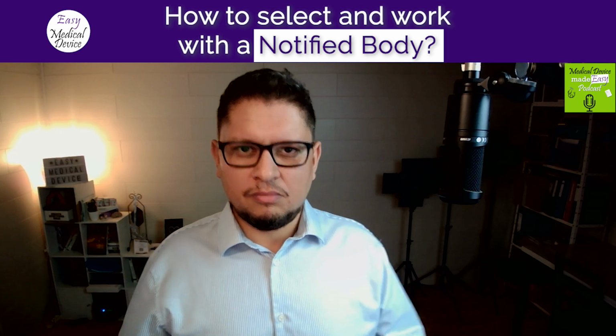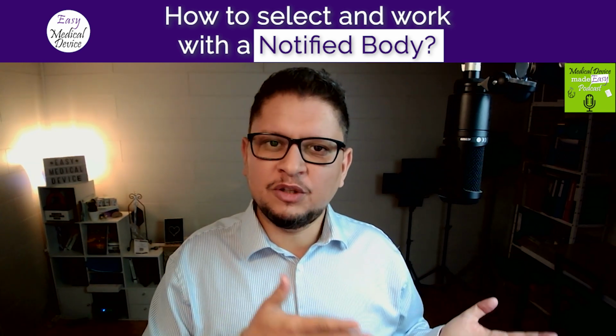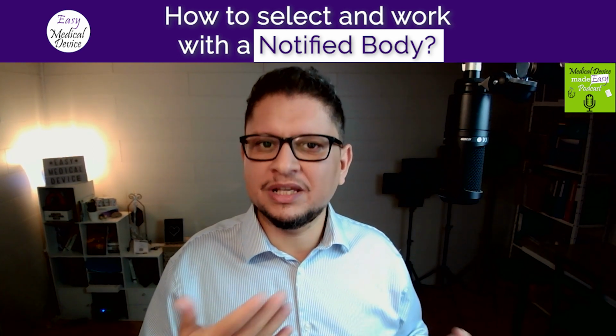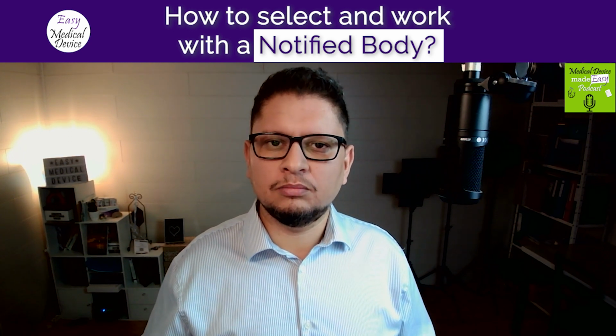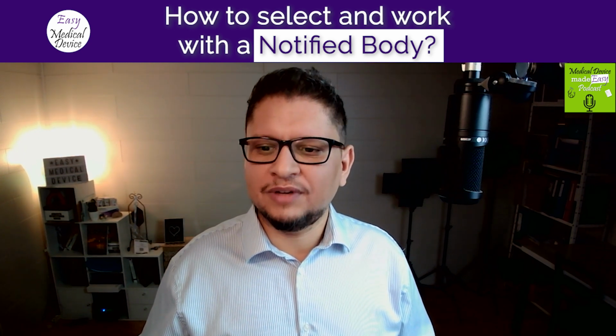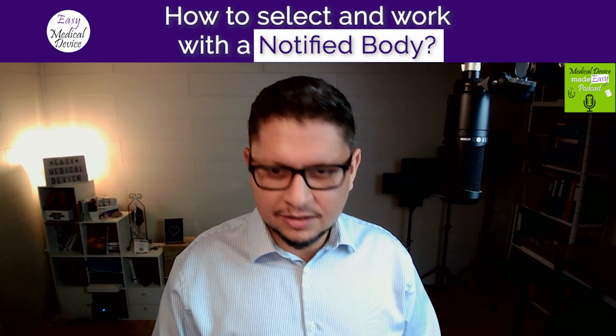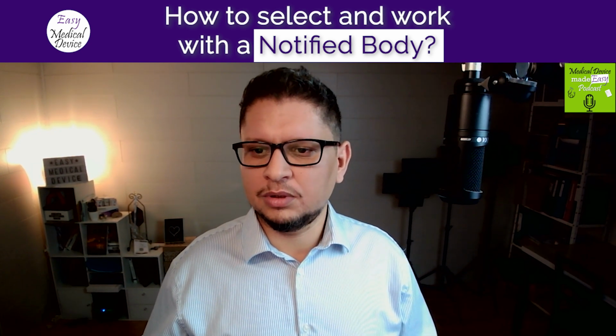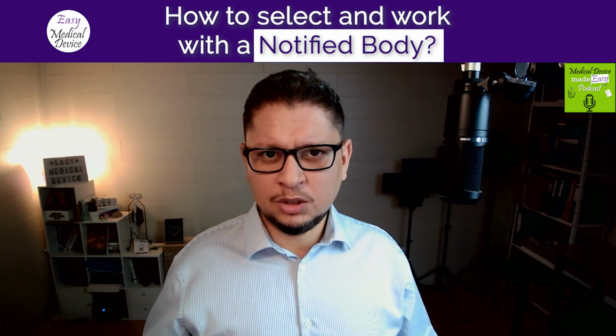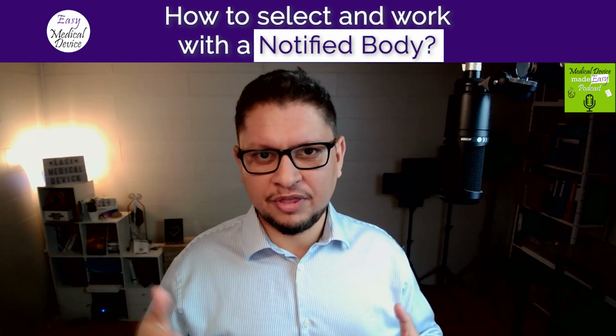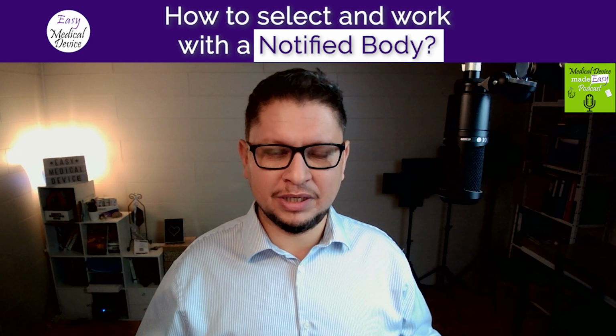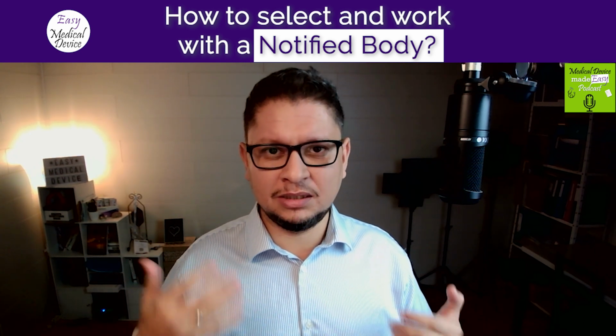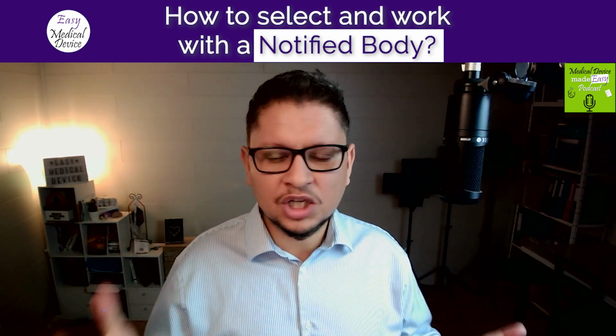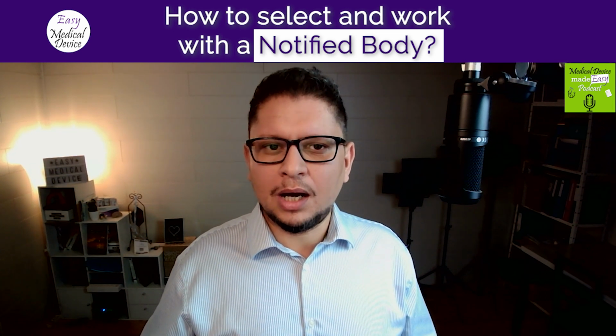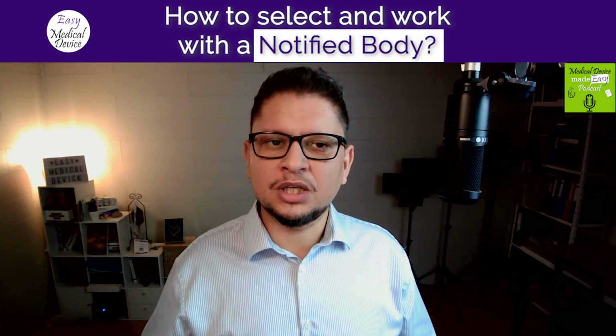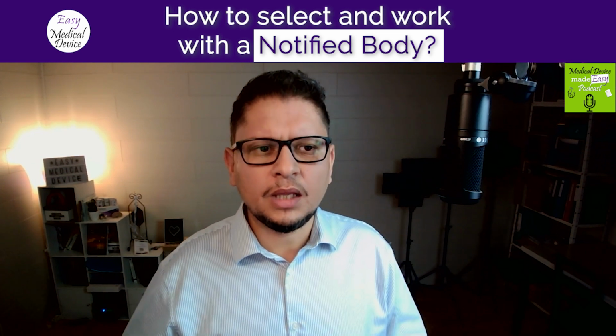Then they take your technical file. I have made a video on how you should normally present your technical file to the notified bodies. You can find it in the show notes; I will place it there. Mainly you send them your technical files, they review everything and check that everything is fine: the preclinical data, the biocompatibility, the GSPR, etc. They check everything. Then you also provide them the clinical evaluation documentation, and they check everything.